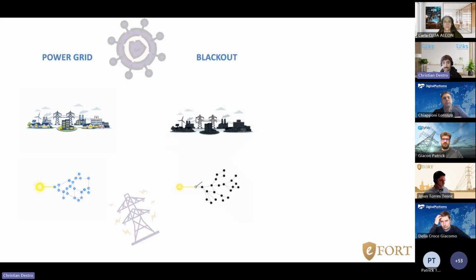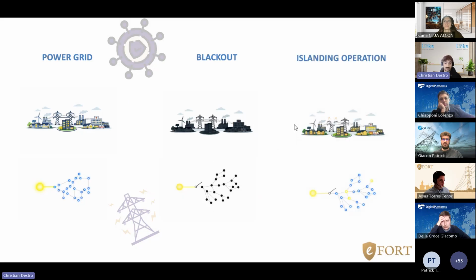Let's imagine a normal power system supplied from high voltage or medium voltage down to low voltage levels. Suddenly a fault occurs, or a disconnection maneuver is performed for maintenance. Two things can happen: blackout, meaning loss of supply, or islanding operation—a condition in which a portion of the electric network continues operating autonomously after being disconnected from the main grid.